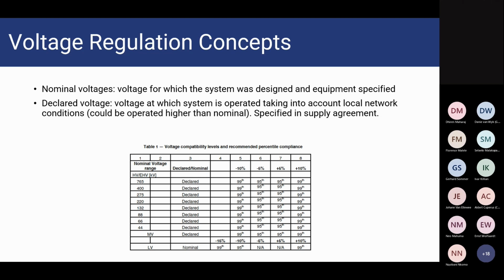And this is normally specified in the supply agreement. So the first thing that's important for a voltage assessment is that your voltages are assessed compared to the declared voltage and not your nominal voltage. If you look at Table 1, copied from the NRS 048, you'll see that at all the nominal voltage levels, so we have 44 kV, MV, which are 11 and 22 kV, all of the voltage levels on MV and up compare your RMS voltage to the declared voltage, which is mostly specified in your supply agreement. On LV, it's a bit different. On LV, we compare voltage to the nominal voltage and not the declared voltage.